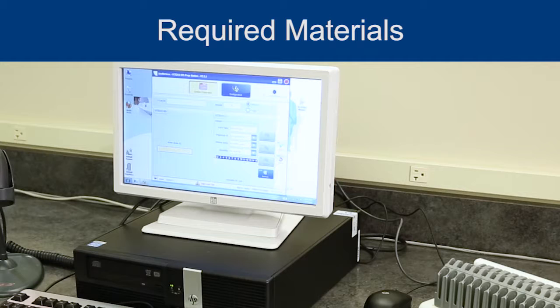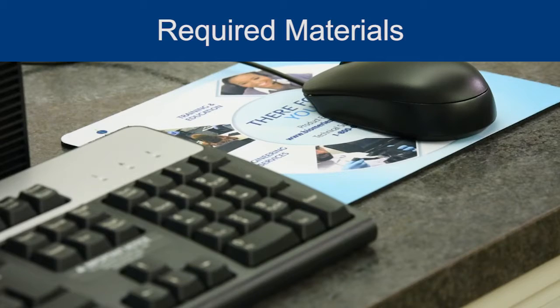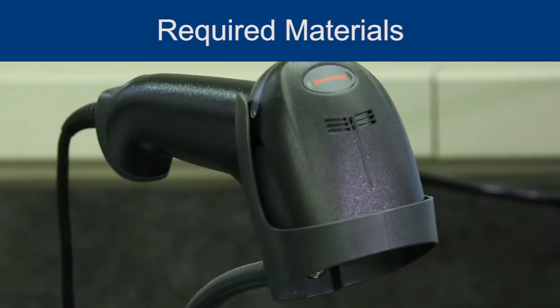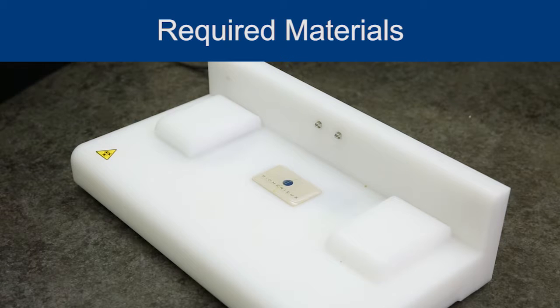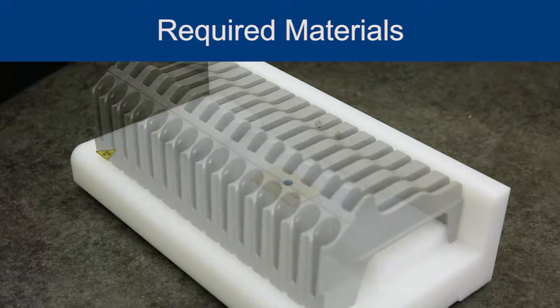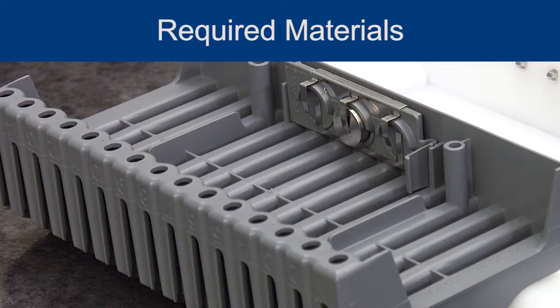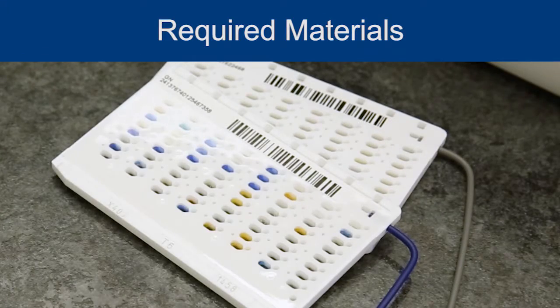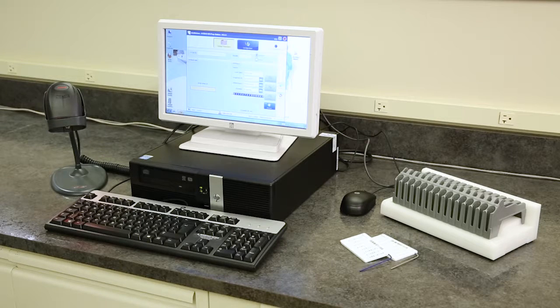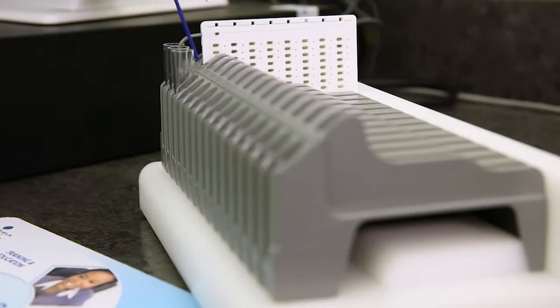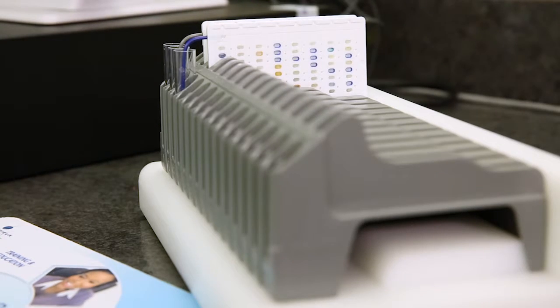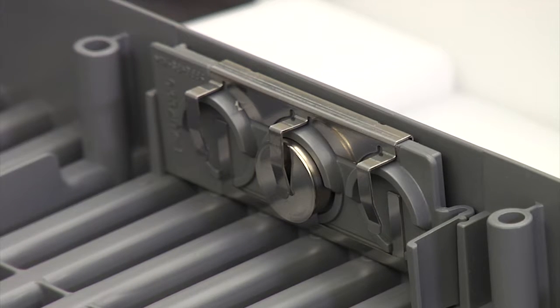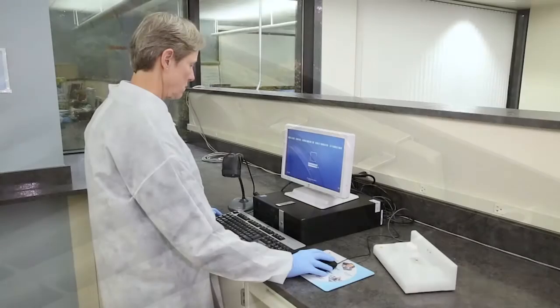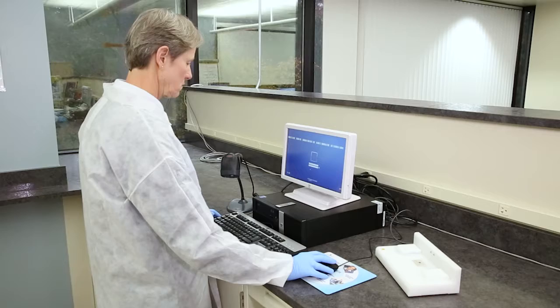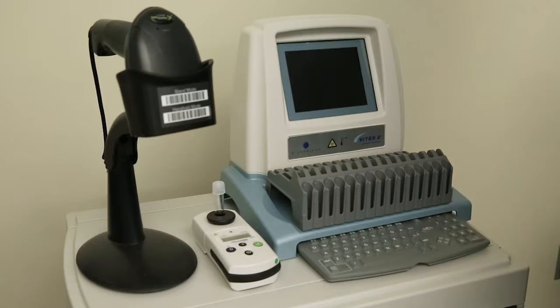Required materials: a computer with VITEK PrepStation software, a monitor, a keyboard and mouse, a barcode scanner, a cassette docking station, also referred to as the VITEK MS PrepStation hardware, a VITEK 2 cassette with button memory module, and VITEK 2 test cards. The VITEK MS PrepStation software with a connected cassette docking station can be used to link specimen information to VITEK 2 test cards. This information is then transferred via the cassette memory button to the VITEK 2 system. The VITEK MS PrepStation software with cassette docking station is used in place of the smart carrier station.